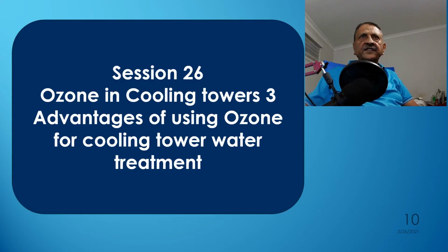This session will address in detail the advantages of using ozone against chemicals in terms of the microbiological quality, reduced water usage, reduce or eliminate chemical usage, eliminate frothing, eliminate slime, reduce or eliminate scaling, and reduce corrosion. You also reduce the downtime and maintenance costs and lengthen the life of the cooling tower. It improves efficiency and increases the rate of the heat transmission.